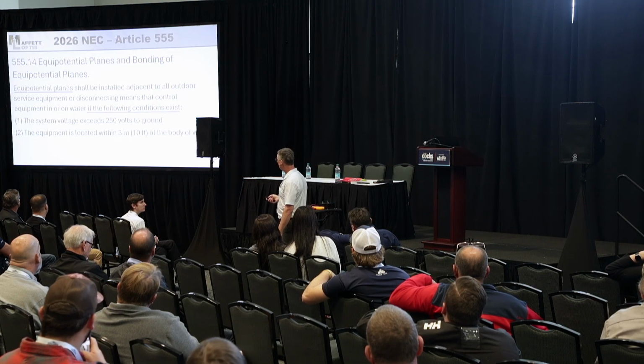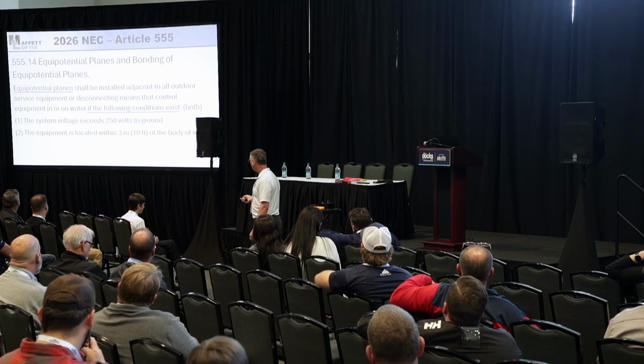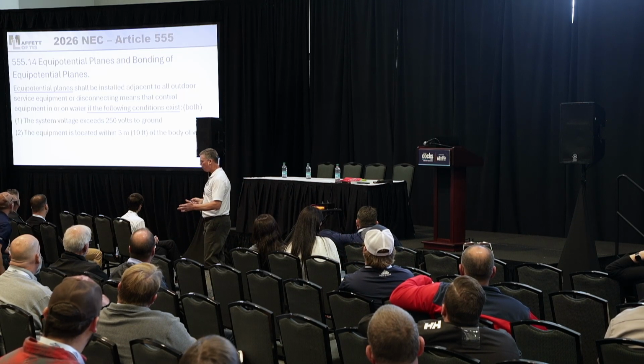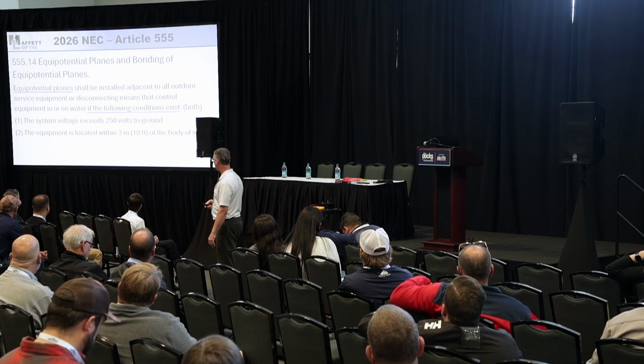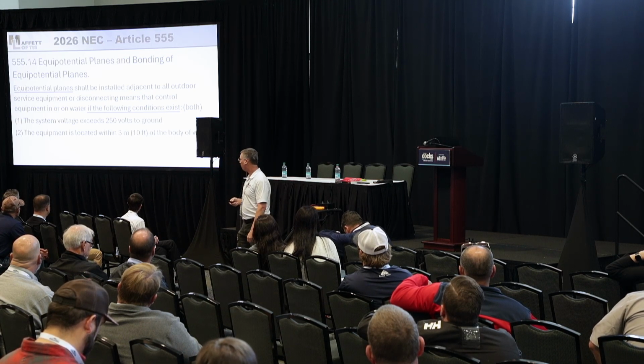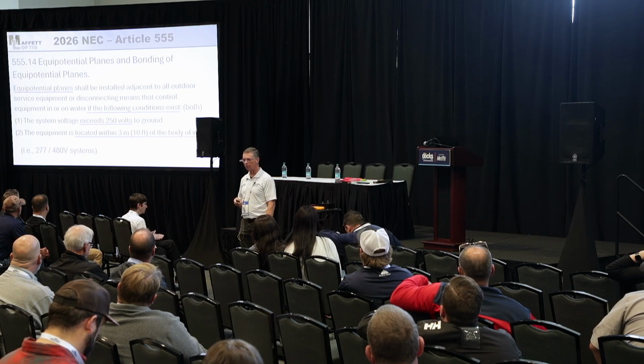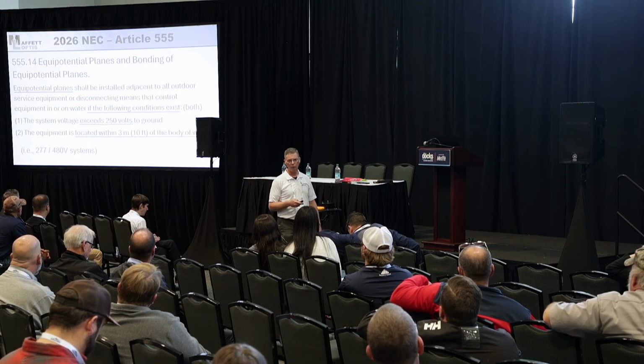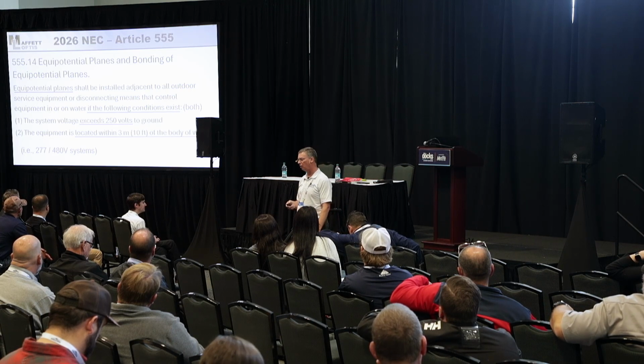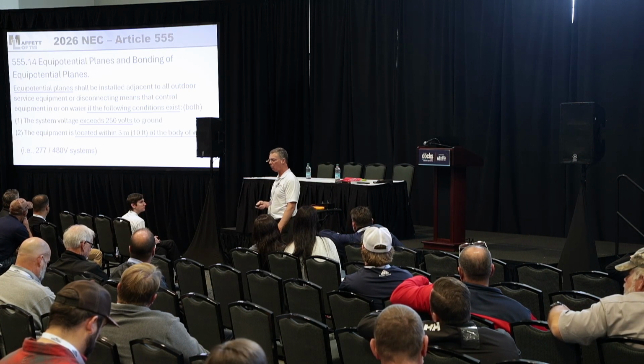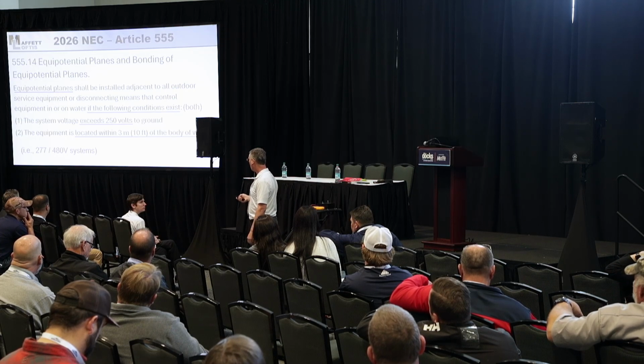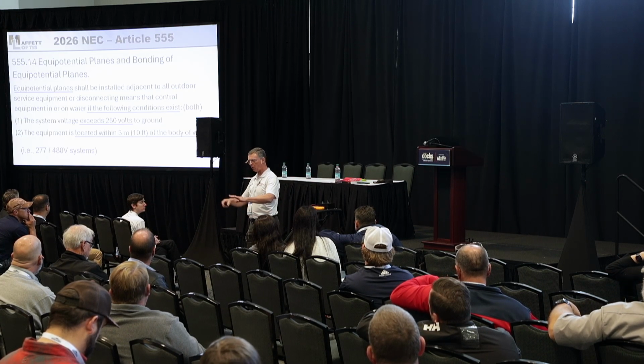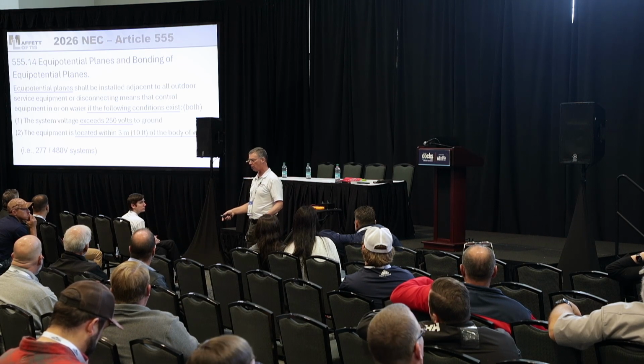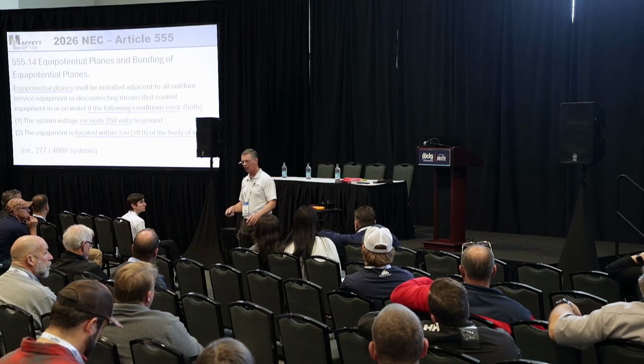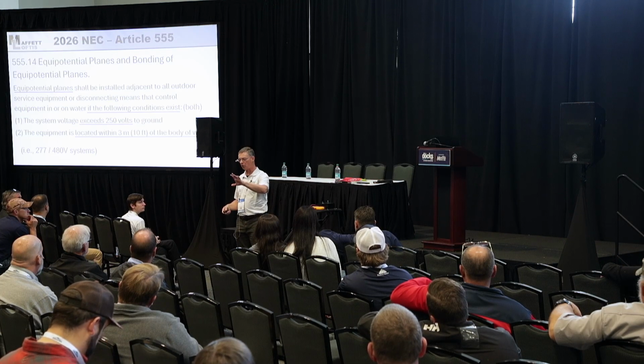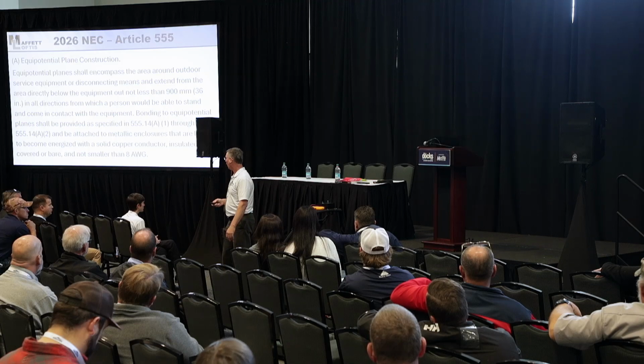But what we're saying is that we want that equipotential plane to extend in basically the following conditions. If the system voltage exceeds 250 volts, which is basically a 480 3-phase system. If it's a standard 120/240 volt system, you don't have to worry about the equipotential plane. We didn't want to be overbearing with this code. But anywhere within 3 feet of that piece of service equipment has to have that equipotential plane. I'll show you a graphic of that. If you have an upland piece of gear that's 480 3-phase, 3 feet away from it has to be this plane.